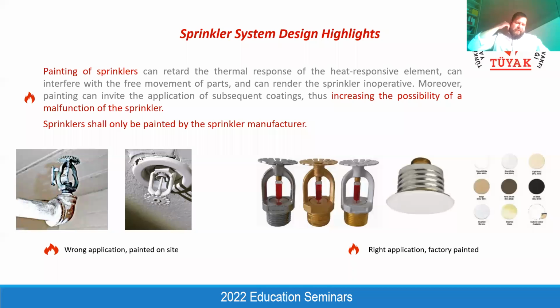If you, as an architect, would like to have some colored sprinklers, for example black or silver or yellow, you need to inform the manufacturer. They will paint the sprinkler head at the factory, and then it is allowed. But the manufacturer shall be informed from the beginning of the project, because it takes time to manufacture sprinkler heads with different RAL codes. But it is possible. If you define the colors for separate areas, you can procure these sprinkler heads with different colors, and you will achieve your design.